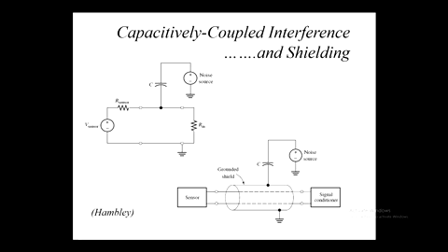All right, and here we are again with a capacitively coupled signal coming into a typical circuit, and with the shield, the capacitive coupling is bypassed directly to ground via this low impedance grounding shield. You've seen these shields, they're kind of a mesh of wire that encapsulates the signal lines, and if we're lucky, the signal lines are not separate and we don't use the coax cable as a return path, but we can do that.